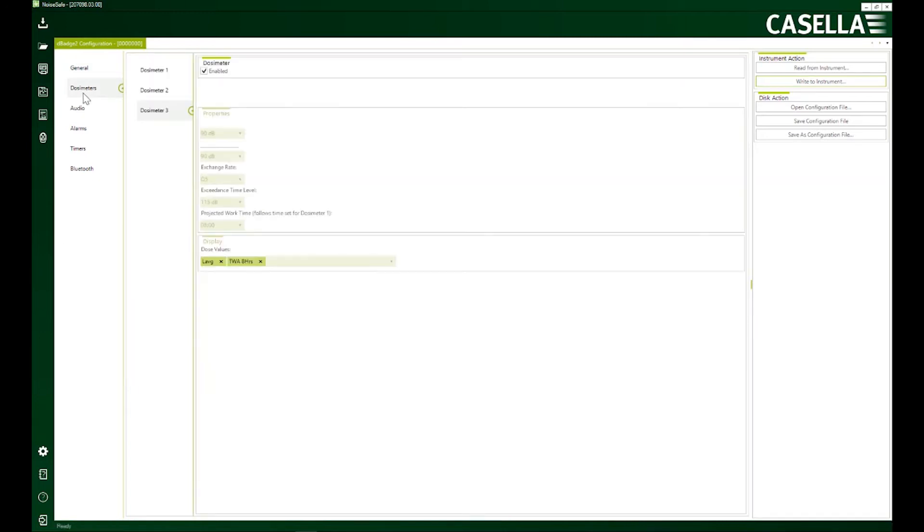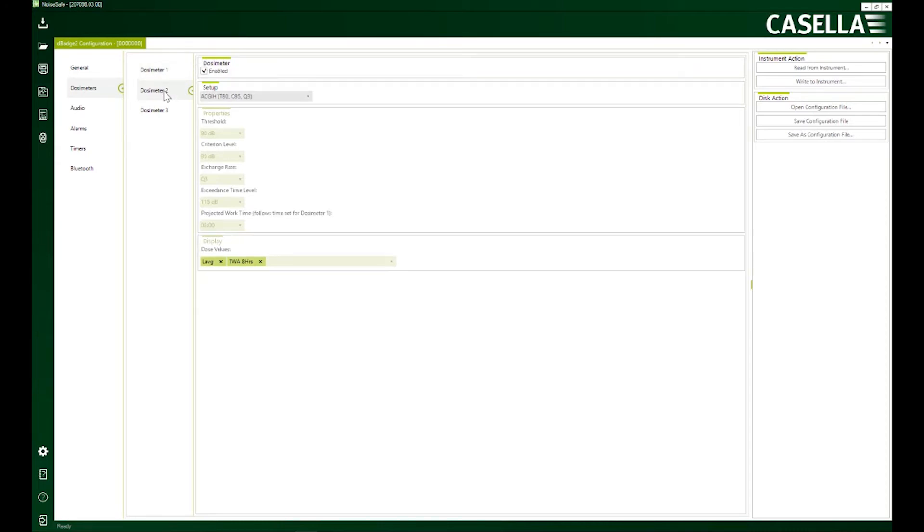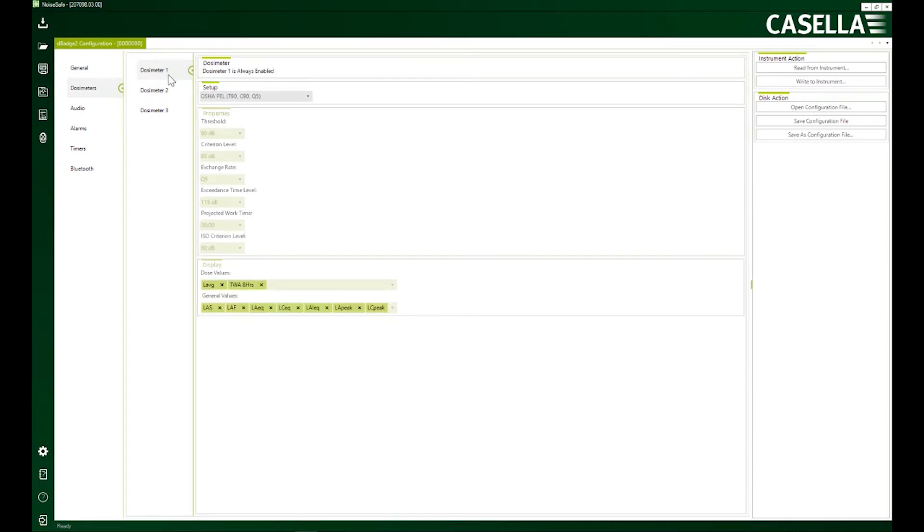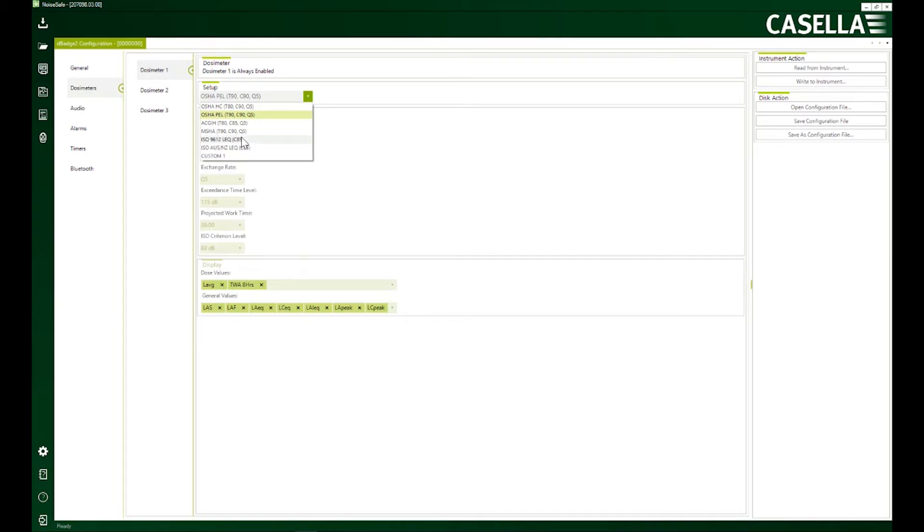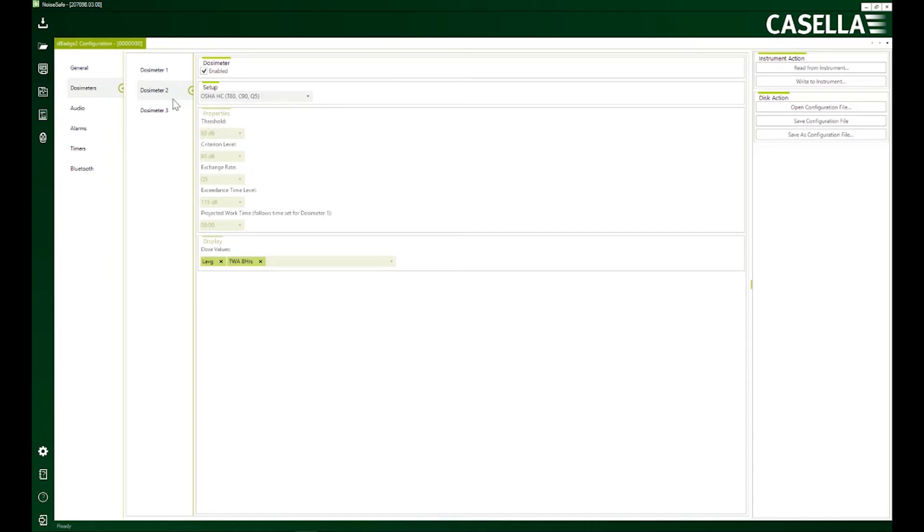I'm going to go to dosimeters. Although it is just one dosimeter, you have options available to have readings according to various standards. Dosimeter one is always enabled. So if my prime criteria is to have reading according to ISO standard, I'm going to select it here. But at the same time, I would like to have readings according to OSHA hearing conservation method.